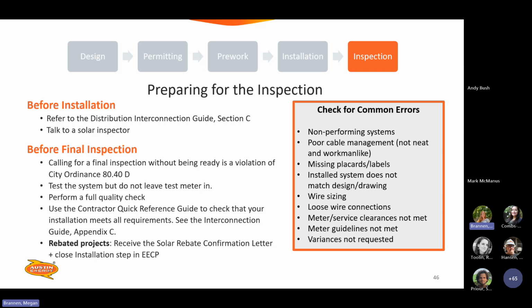Do test the system, but do not leave the test meter in. Of course, that'll be really obvious when the inspectors get to site, so just keep that in mind. Do perform quality checks and just make sure everything, again, is kind of buttoned up. All your i's are dotted and t's are crossed before we come out there. And then feel free to use the contractor quick reference guide in the DIG to make sure that your installation meets all the requirements. Again, you'll find that in the interconnection guide in Appendix C. For rebated projects, make sure you receive the solar rebate confirmation letter prior to installing. Do not install without a confirmation letter that your rebate is approved. And then, of course, make sure to close the installation step in EECP before requesting that inspection, so everything's ready to go.